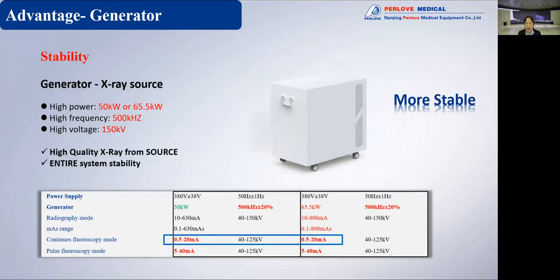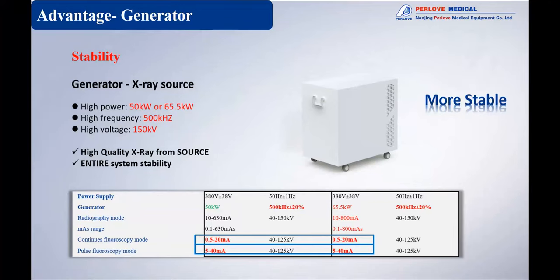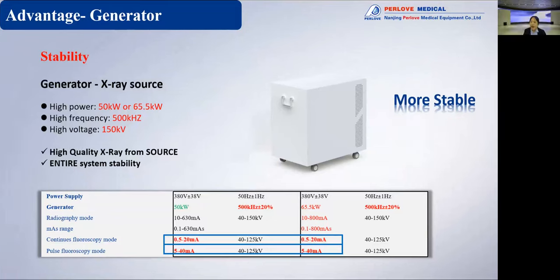Please pay attention to continuous fluoroscopy modes. At the same time, for these manufacturers, their pulse fluoroscopy mode will be less than 5 milliampere. But ours can be from 5 to 40 milliampere. So for some fluoroscopy examinations, the equipment can also offer very stable working.